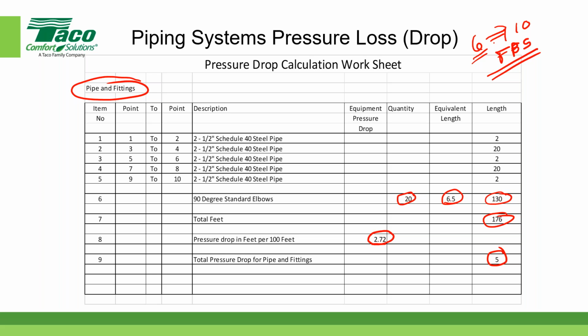In order to increase the life expectancy of the pipe. So obviously cost comes into play, right? If you can get away with a 2.5 and you put in a 4, well, I think we can all agree it's going to cost a little more. But it also lowers how much head you're going to put on the pump. So sometimes that comes into play.